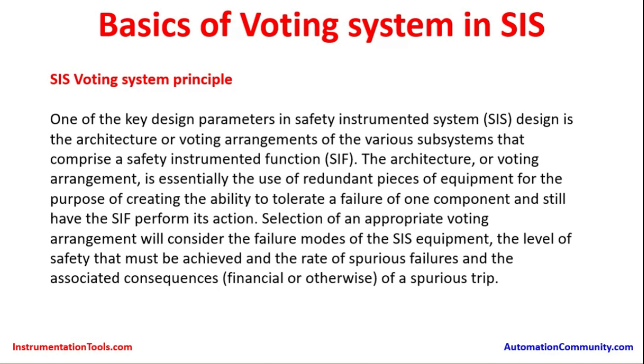We want the safety instrumented function performing at all times, and we also want to keep some redundancy — some kind of availability in case of one instrument failure or one valve failure, so the other one should take over. That is why during the design stage, it is carefully engineered to have a 1 out of 2 or 2 out of 3, or other different types of voting systems.